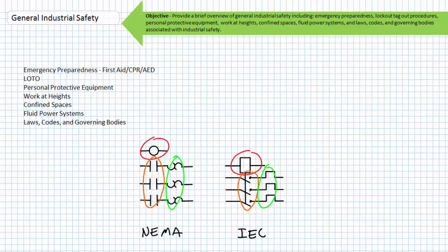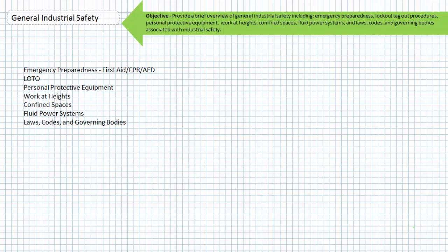Consider a specific application in which there are nine divisions of available NEMA contactors and for the same application, 14 divisions of IEC contactors. The NEMA contactors are more robust, but they're normally bigger and more expensive. The IEC contactors are lightweight and less expensive, but they don't have as wide of an operational range.